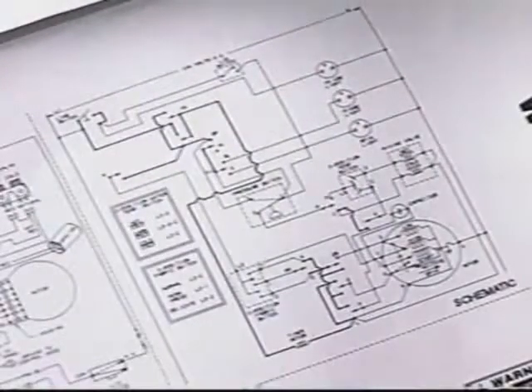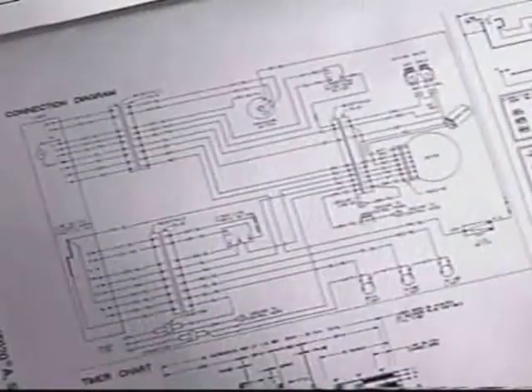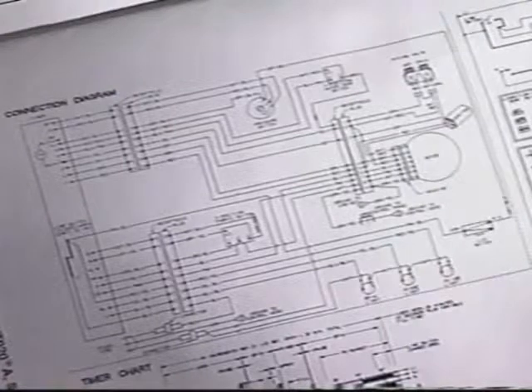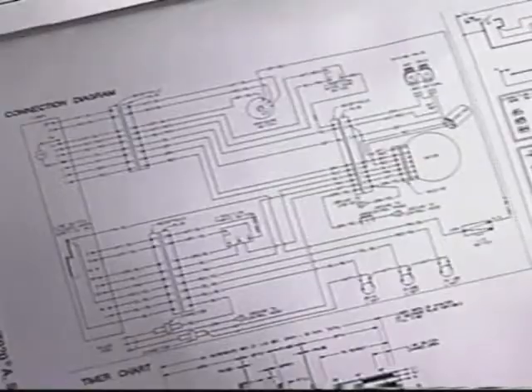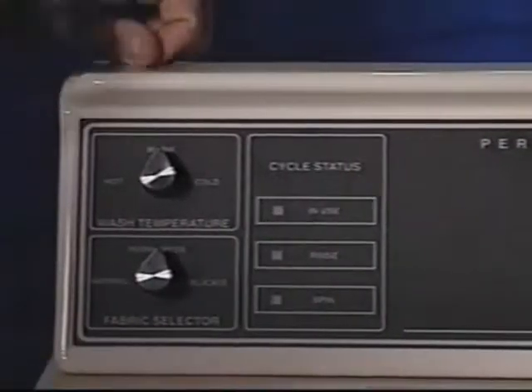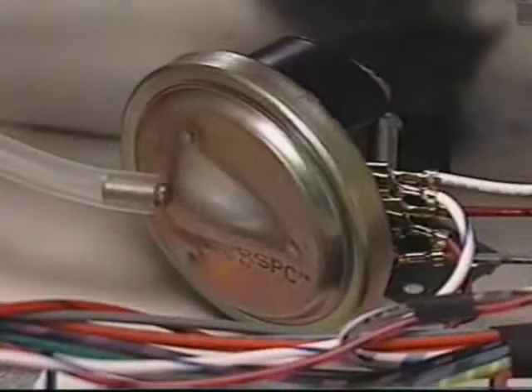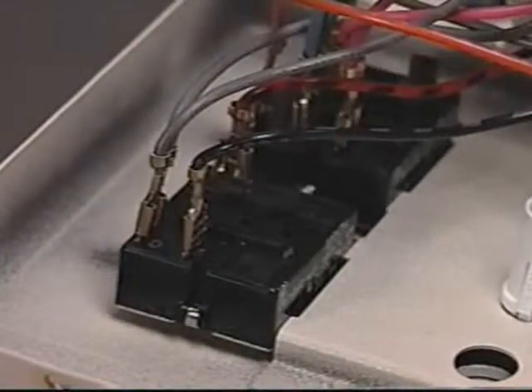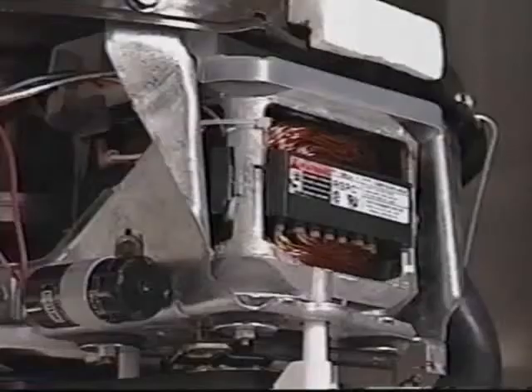The wiring schematic gives us a clearer illustration of the current flow in the electrical circuit of the washer. The connection diagram is the physical diagram of wires, connectors, and electrical components. We'll use this diagram as a location aid. We must be able to recognize the electrical switches and loads in the circuit. Let's identify them. The switches consist of the pressure switch, timer contacts, lid switch, temp selector switch, and fabric selector switch. The motor, mixing valve, and timer motor are the loads. Now we're ready to begin.